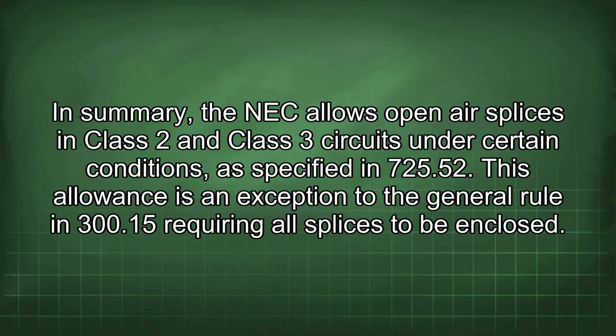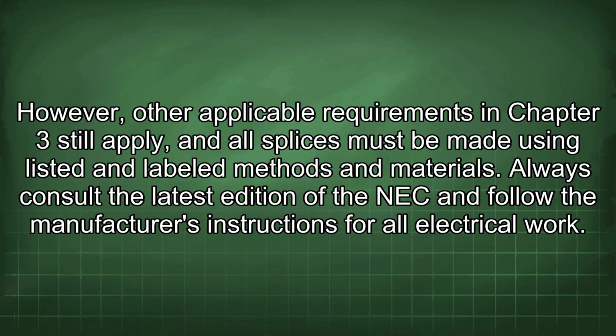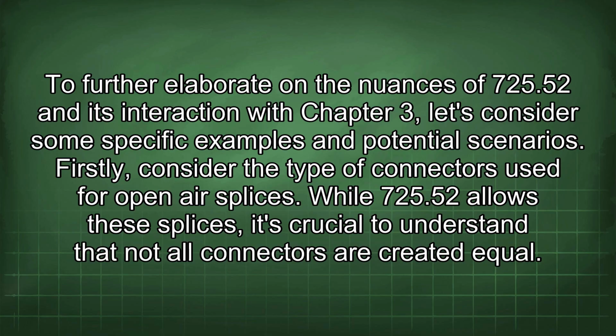In summary, the NEC allows open-air splices in Class 2 and Class 3 circuits under certain conditions, as specified in 725.52. This allowance is an exception to the general rule in 300.15 requiring all splices to be enclosed. However, other applicable requirements in Chapter 3 still apply, and all splices must be made using listed and labeled methods and materials. Always consult the latest edition of the NEC and follow the manufacturer's instructions for all electrical work. To further elaborate on the nuances of 725.52 and its interaction with Chapter 3, let's consider some specific examples and potential scenarios.